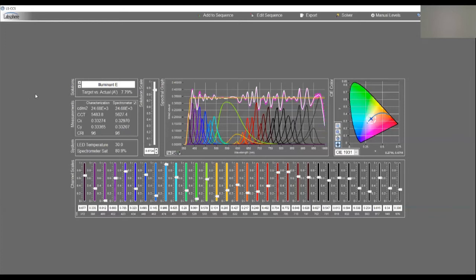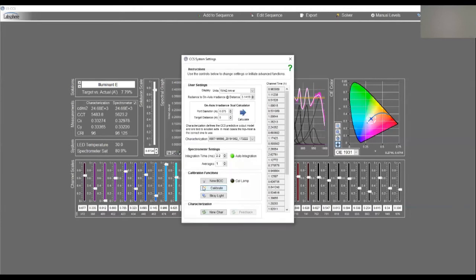So let's say that after a month or two, you notice that the spectral radiance monitor is starting to drift down a little bit, so you want to recharacterize it so you get an accurate reading of the spectral radiance coming through the port. We have this feature in our settings, and you can see here we have calibration functions, and this applies to the spectroradiometer. We also have a recharacterization feature, which I will speak about in a separate video, and I hope you join me for that. So here we have a new baseline offset correction.